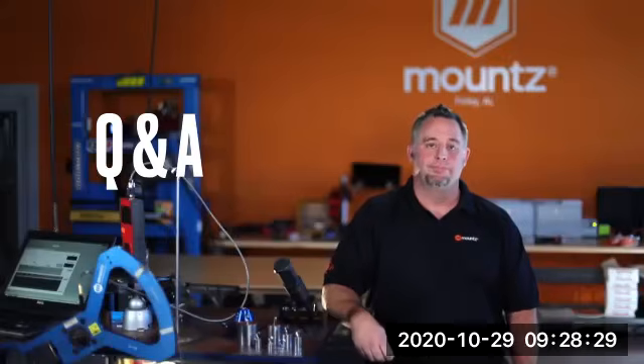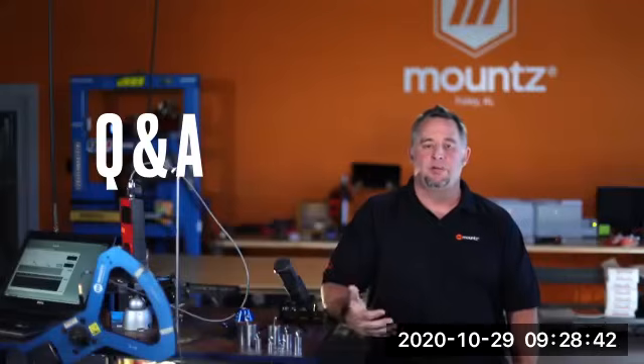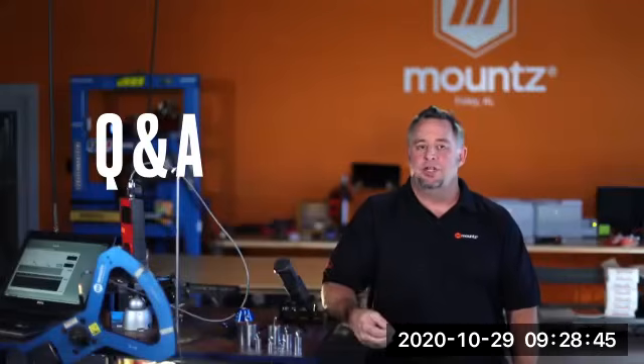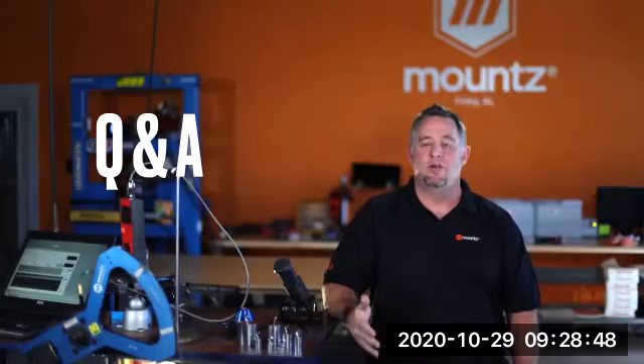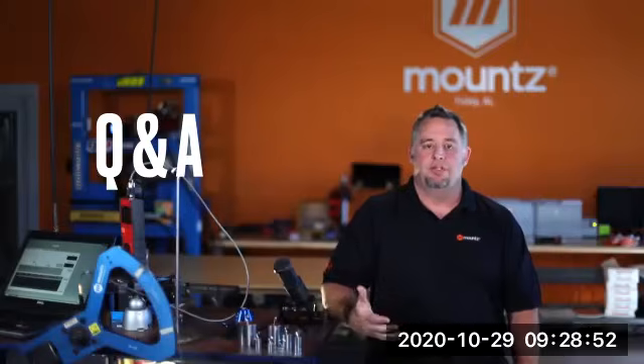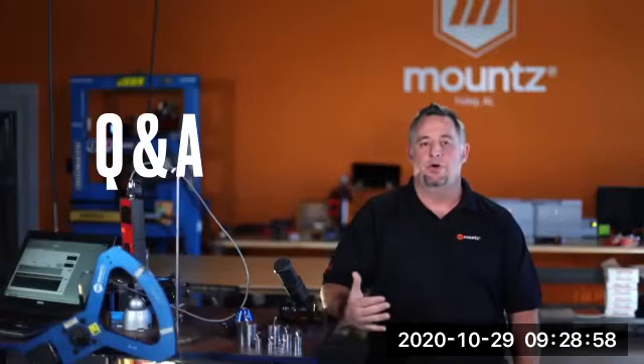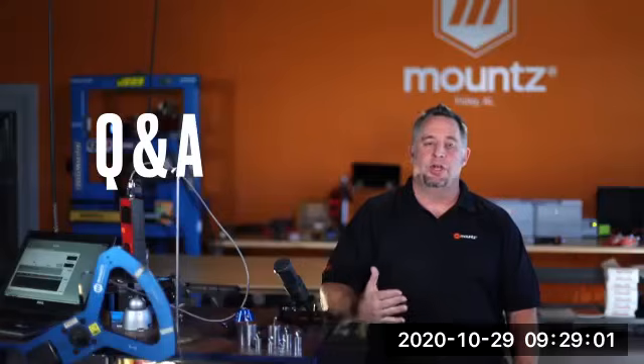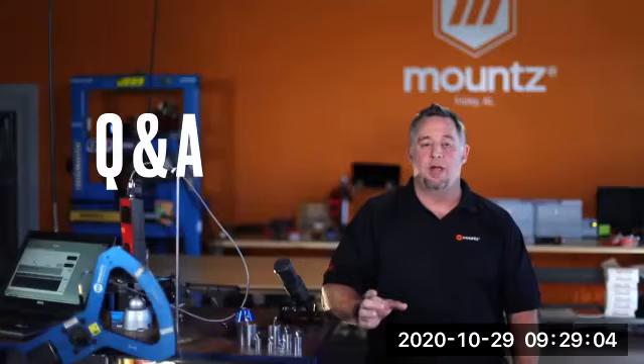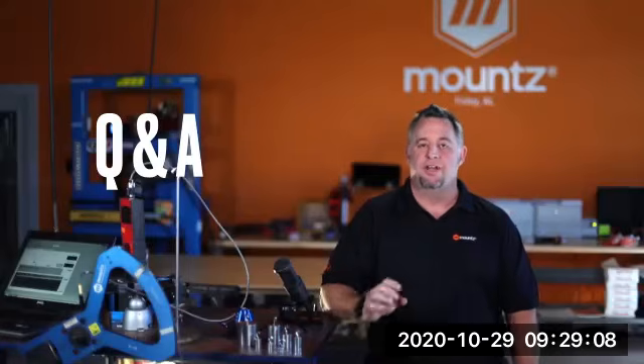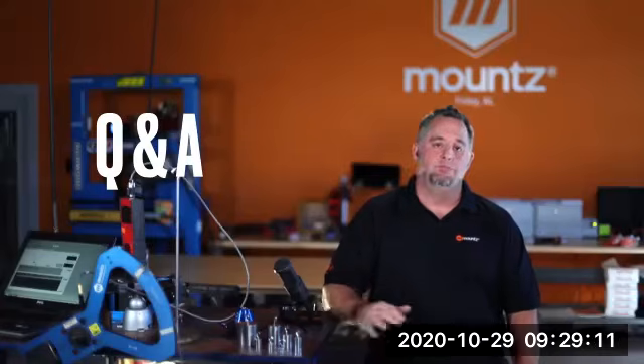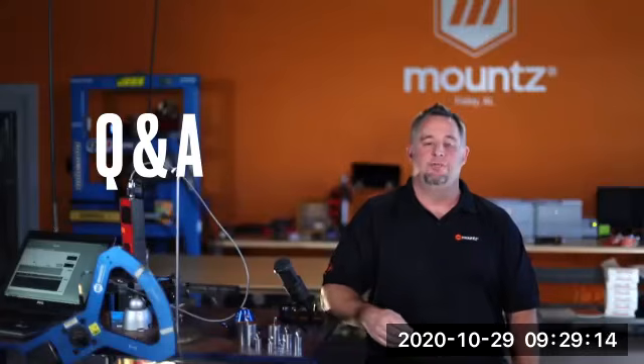I have a question from Paul. What standards would you recommend to run an in-house calibration program? It's going to depend on how much usage there is and the management goals. So if you wanted to do a 3-point calibration every 6 months or a 5-point every 12 months, that's something you can track. If you see any out-of-tolerance issues over an extended calibration cycle, you could go ahead and halve the time and see how that affects the overall pattern within that particular sensor.